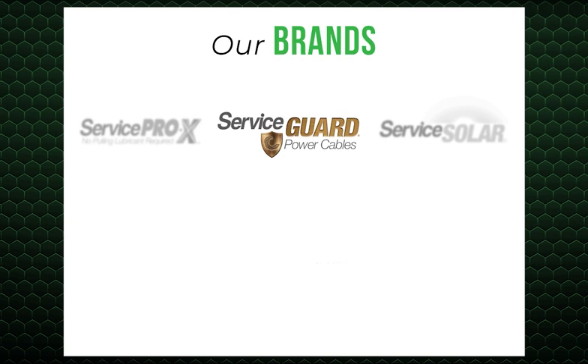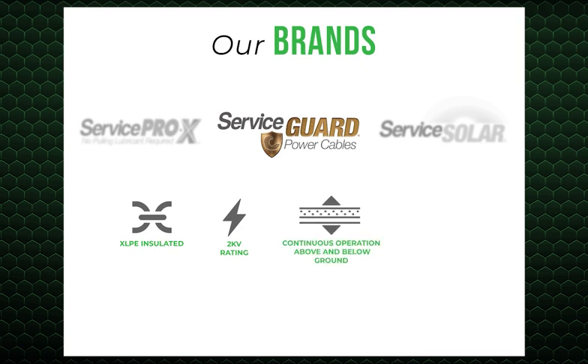Service Guard flame-resistant XLPE insulated single conductors are suitable for use at operating voltages up to 2,000 volts in standard circuits. The conductors are temperature rated at 90 degrees Celsius wet-dry for continuous operation above and below ground, and cold temperature rated at negative 40 degrees Celsius. Service Wire's line of power cables include 2 kV rated RHW-2 and 2 kV rated photovoltaic.